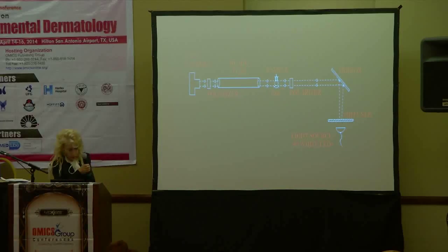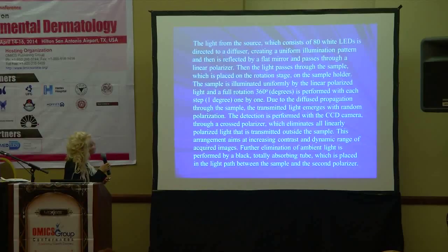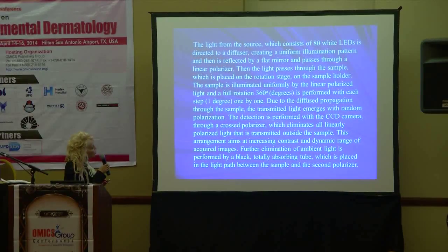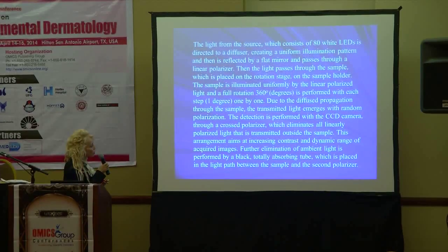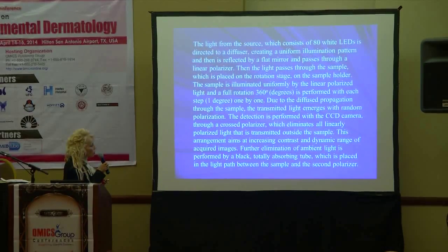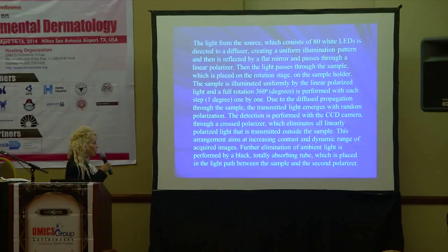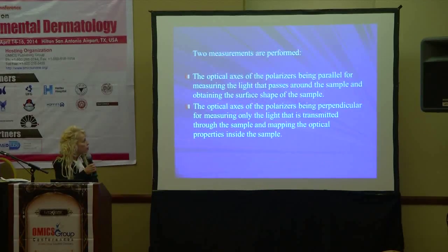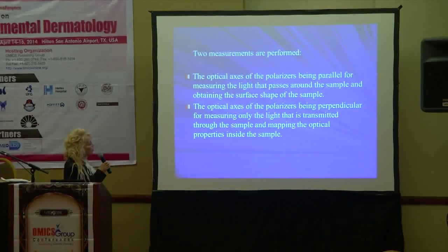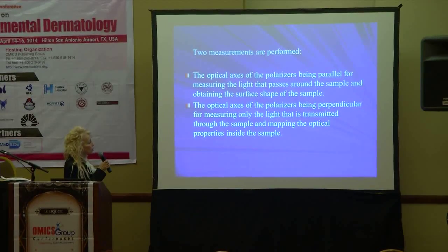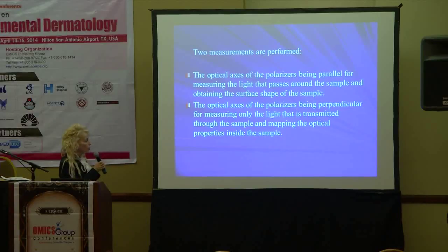Here again is our system. The light from the source consists of 80 white LEDs, going to a diffuser, and passes through the sample. The sample is illuminated uniformly in linearly polarized light and the full rotation takes place. Due to diffuse propagation through the sample, the transmitted light emerges with random polarization. Detection is performed with a CCD camera through a cross-polarizer, which eliminates all linear polarized light transmitted outside the sample. This arrangement aims at increased contrast and dynamic range of acquired images. A black totally absorbing tube, placed between the sample and the second polarizer, eliminates ambient light. The optical axes of the polarizers are parallel for measuring light passing around the sample and mapping surface shape, and perpendicular for measuring only light transmitted through the sample and mapping the optical properties inside.